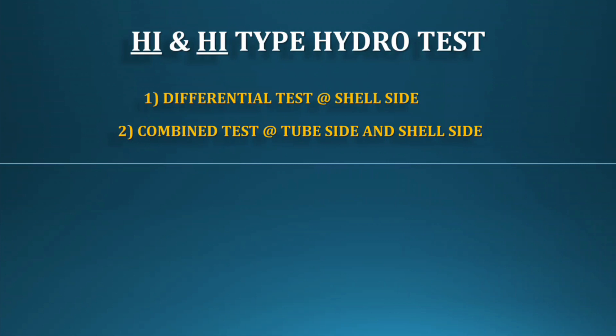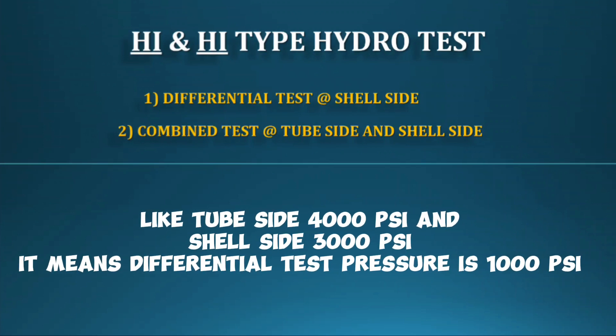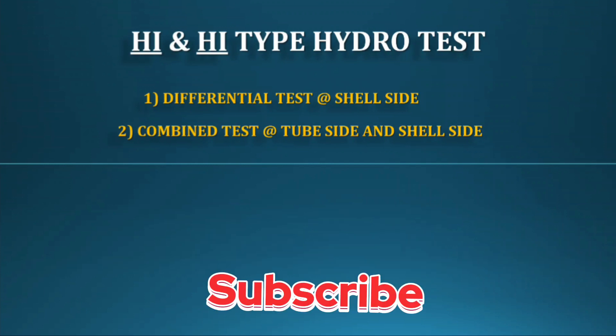First, you should know what a differential test is. It means the differential test pressure between shell side and tube side. For example, if tube side is 4,000 PSI and shell side is 3,000 PSI, then the differential test pressure is 1,000 PSI, and it will be done on the shell side only.